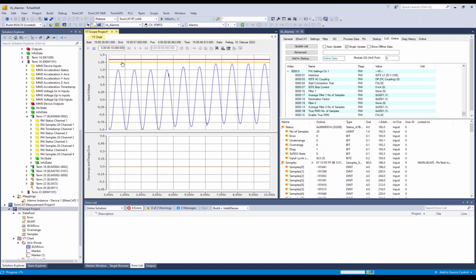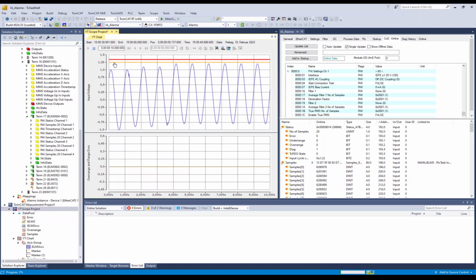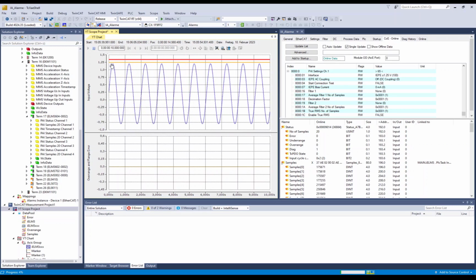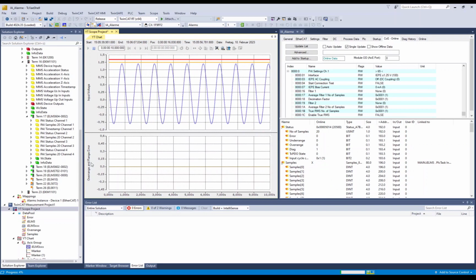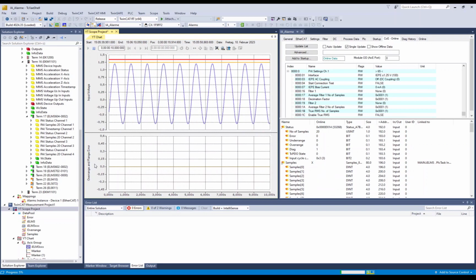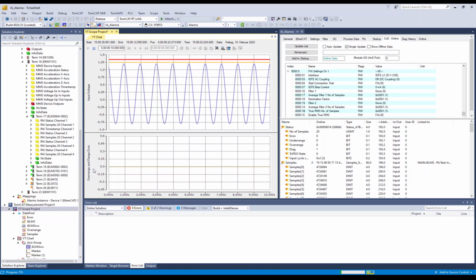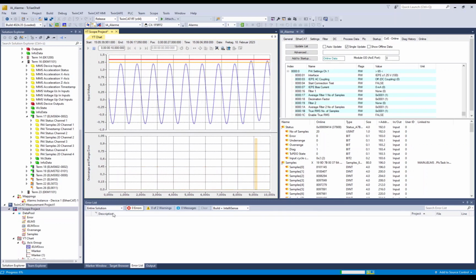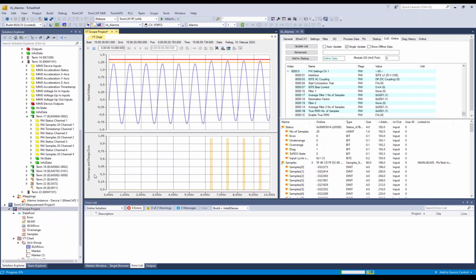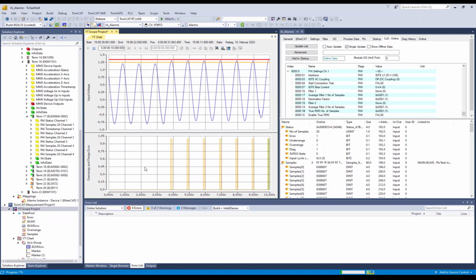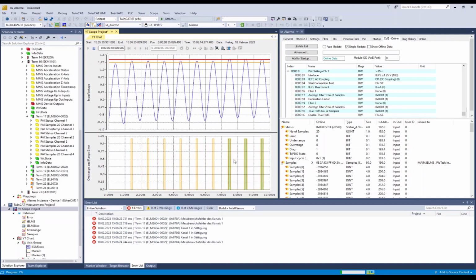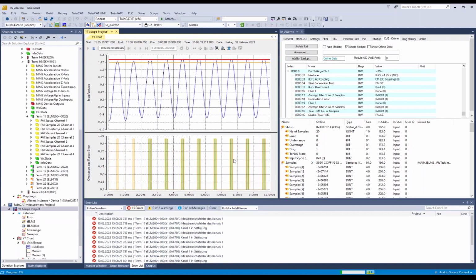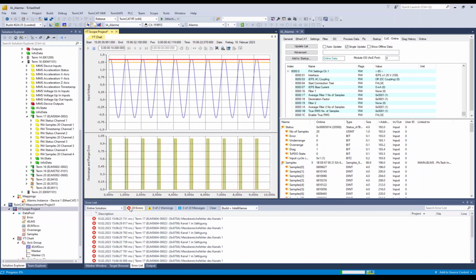And I've created two markers here at 1.25 volts. This is an overrange, and 107% of the measurement range is related to a so-called range error. And as soon as one of these bits gets too high, we will see an error in the error list in TwinCAT. So I will now see that exceeding here, and also if I have the range error, I will have 2 bits, and the range error bits are sent as an emergency to the TwinCAT error list.